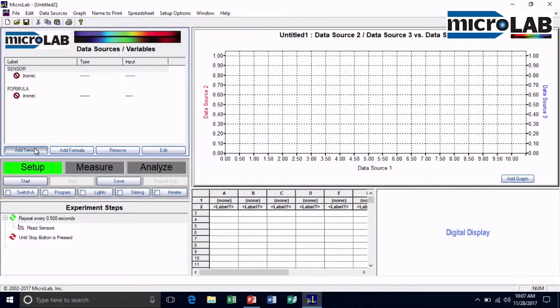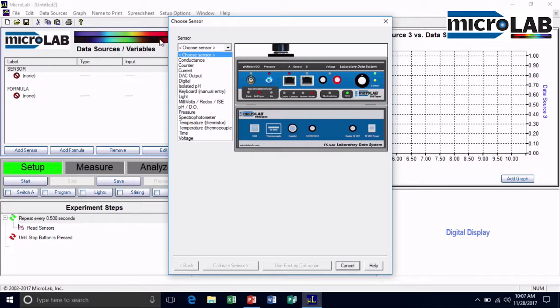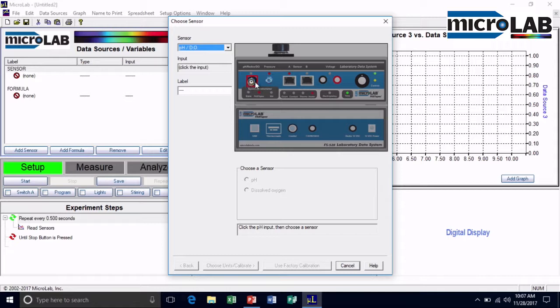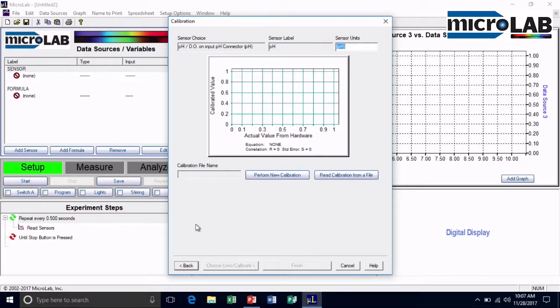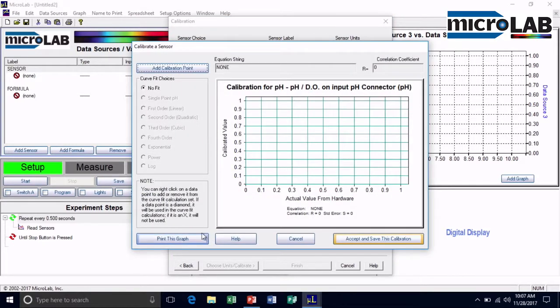I'm going to add a sensor and we're going to add a pH sensor. So I look down my list here and it says pH or dissolved oxygen. That connects here to this BNC connector. I'll click it so the software knows I know where I'm going to plug it in, and I'll choose pH. Now, let's calibrate it. And I get a choice here. I can either read a calibration from a file or I can perform a new calibration. We're going to calibrate this, so I'll click this.